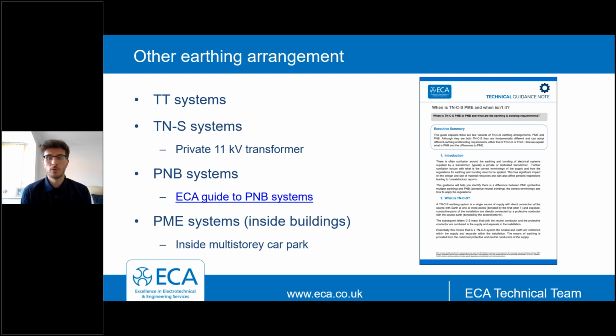So we've looked at how there are additional requirements where the EV charge point is supplied from a PME system, where that equipment is to be used outdoors. However, if we have other earthing systems, it could significantly simplify the design. So this could be for maybe TT or TN-S. So I'm going to do an example based on a TN-S system where there is a private 11 kV transformer. So we know on the site, maybe it's a large commercial or large industrial premises, that we've got a dedicated, reliable TN-S system.